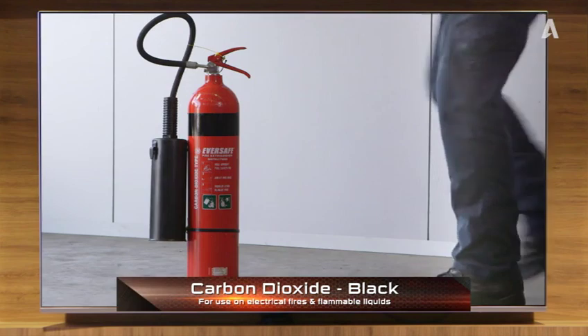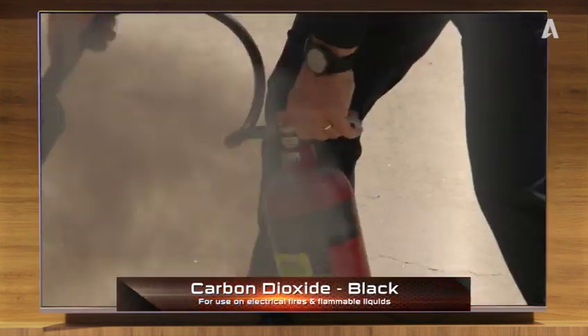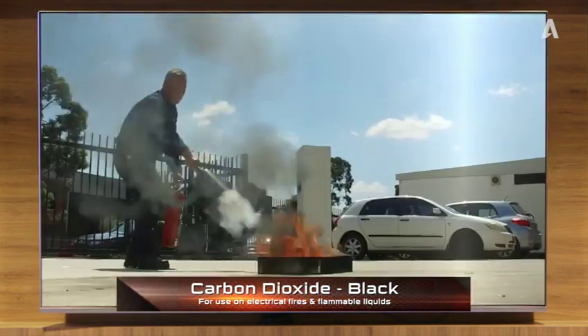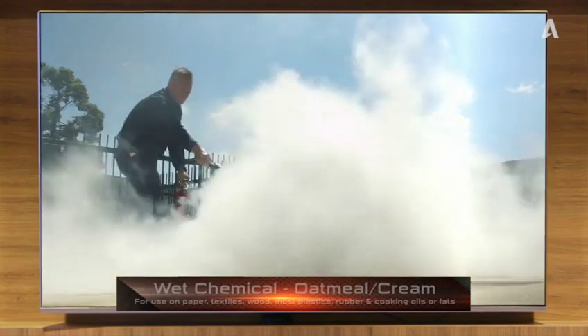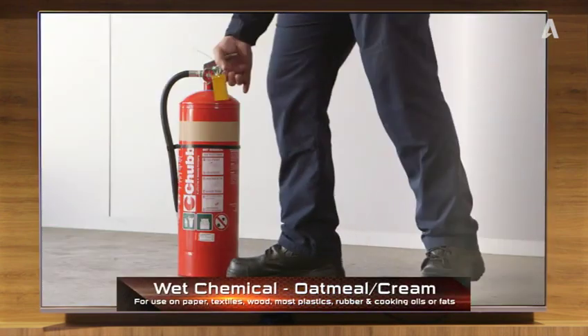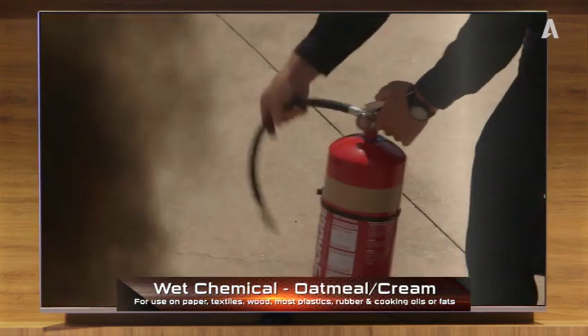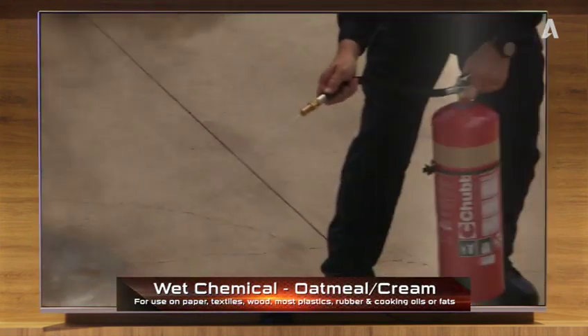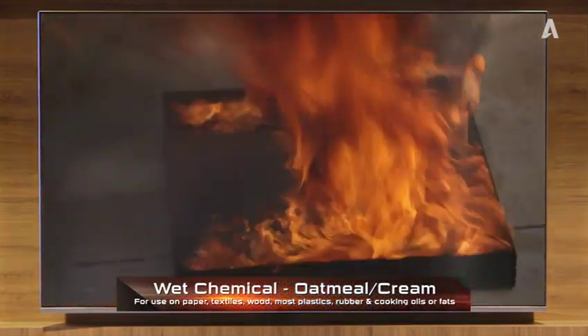For electrical fires and flammable liquids, use a carbon dioxide extinguisher with a black band. And this one with the oatmeal coloured band is a wet chemical extinguisher for paper, textiles, wood, most plastics, rubber and cooking oils or fats.